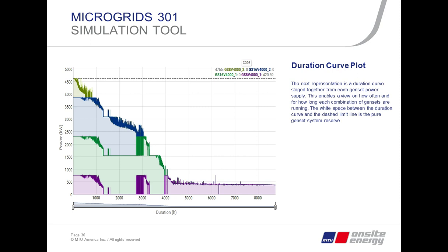And the purple on the bottom, as you said, is basically the same 760 kW unit as the brown on top. We can see that unit is going to run continuously throughout the year, and at some portions, especially during the night, that's maybe the only unit which runs. Yes, it shows 4,000, 8,000 hours with no other genset running — that's basically half of the year in terms of annual run hours. We just need one genset to support the load.